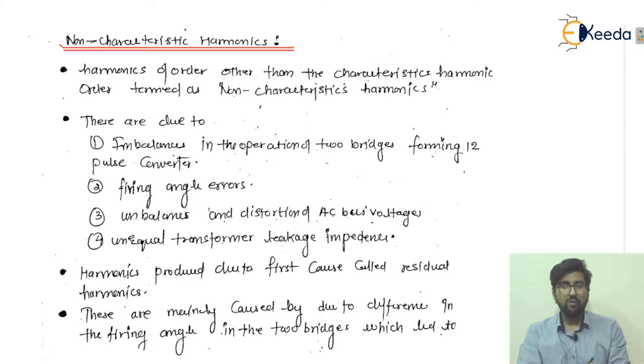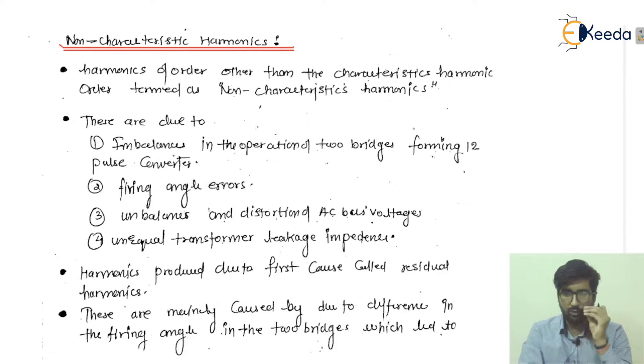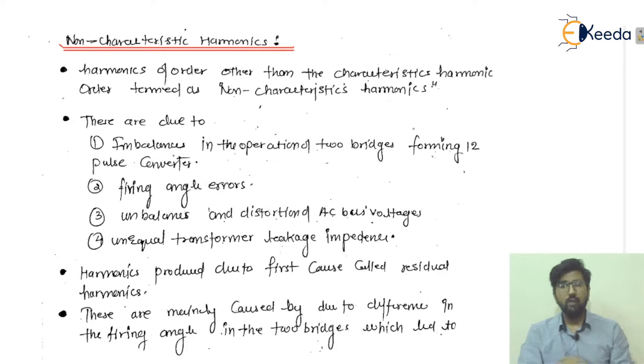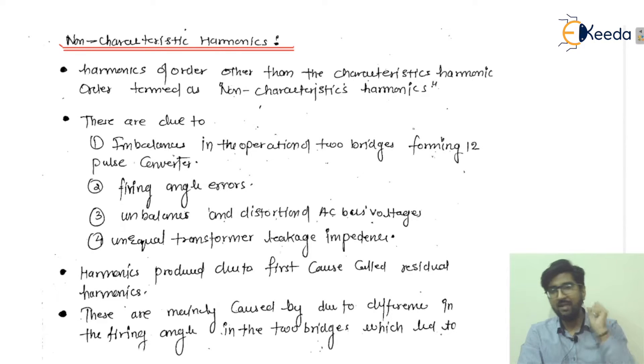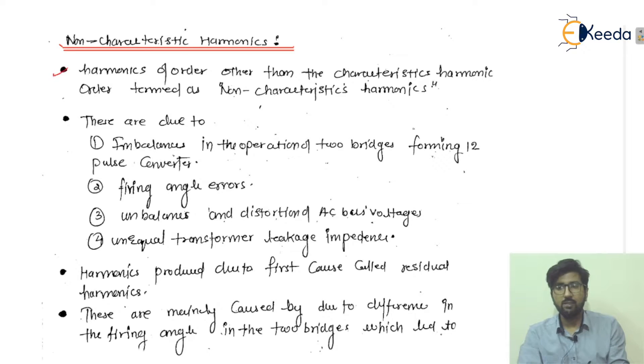To understand non-characteristic harmonics, you first need to understand characteristic harmonics. Characteristic harmonics simply follow one mathematical formula: NP ± 1, where N is an integer and P is the pulse number. Any harmonics that do not follow this NP ± 1 relation are called non-characteristic harmonics. Characteristic harmonics follow NP ± 1; non-characteristic harmonics do not.